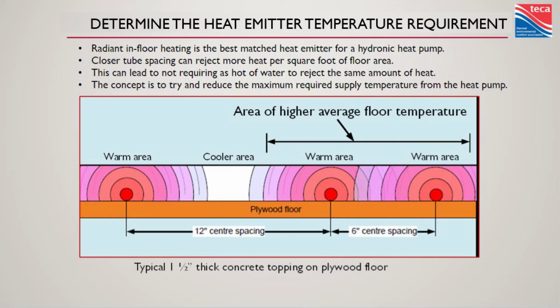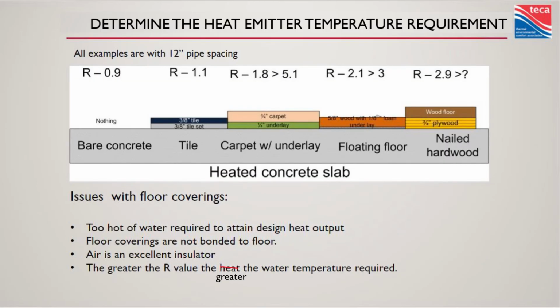To the left, pretty typical standard practice, 12-inch on center spacing. Got our PEX, we've got this stripe of no heat, and then PEX. All these circles represent various different concentrations of heat coming off of that pipe. To the right, we've got 6-inch on center spacing. You'll notice it's not as cold right here. That means our average surface temperature is higher over here than over here without changing the water temperature. Heat output of a radiant panel is based on that average surface temperature. So tighten up that spacing, it'll save you a lot of headaches later. Try to avoid shag carpet and other things that are going to impede heat transfer.